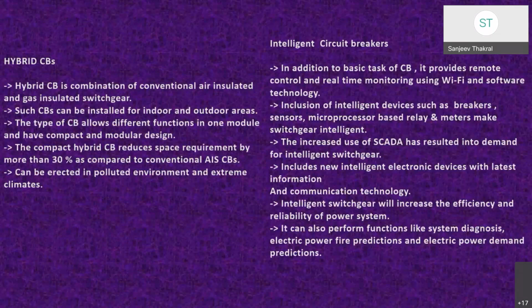Next is the intelligent circuit breaker. In addition to the basic task of the circuit breaker, switchgear technology is becoming intelligent. The increased use of SCADA has resulted in demand for intelligent switchgears. Intelligent switchgear includes new intelligent electronic devices with the latest information and communication technology. Intelligent switchgear increases the efficiency and reliability of the power system. It can perform functions like system diagnosis, electric power fire predictions, and electric power demand predictions by using different sensors.